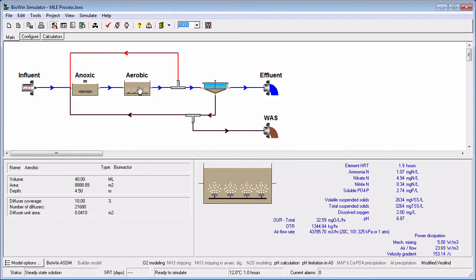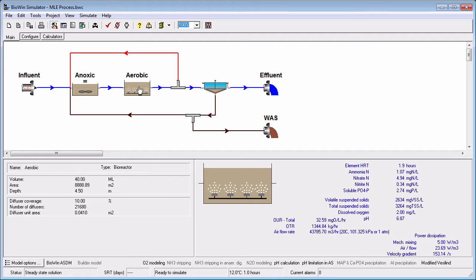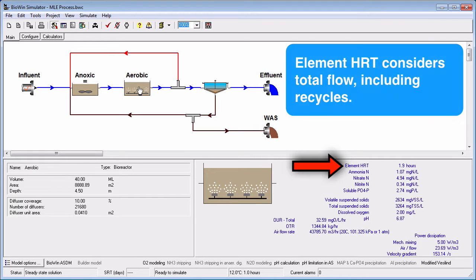The first way is by pointing at elements on the flow sheet. When you do this, the element HRT is displayed in the summary pane at the bottom right of the main BioWin window. The element HRT is calculated by dividing the element volume by the sum of all flows entering the element.